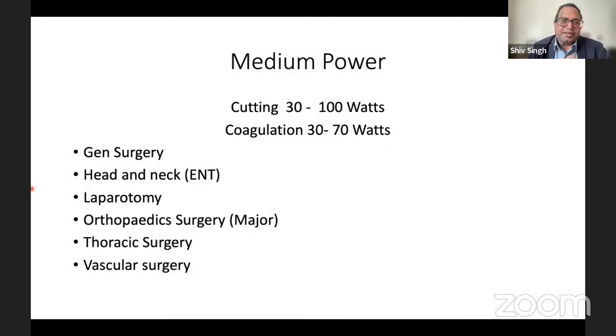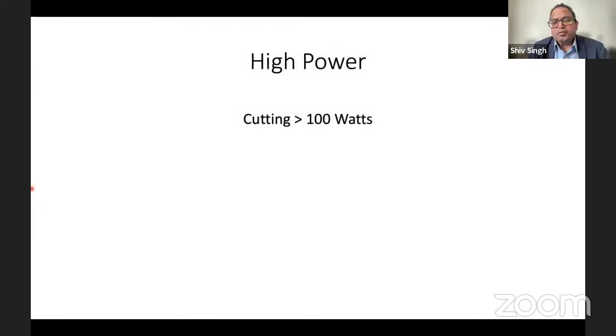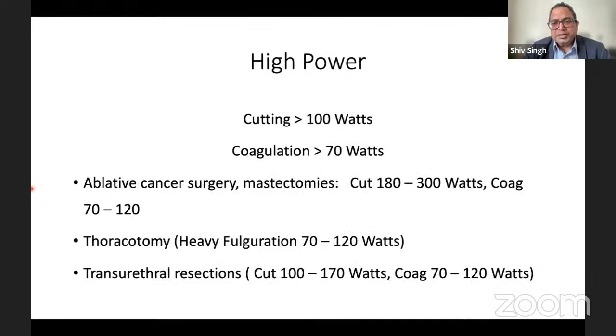It is used in ENT, laparotomies, orthopedic surgery, thoracic surgery, and vascular surgery. But sometimes you have to use very high power, and that's more than 100 watts for cutting and more than 70 watts for coagulation. This is sometimes used in ablative cancer surgeries and mastectomies, where they use 180 to 300 watts for cutting and 70 to 120 watts for coagulation. Thoracotomy, where you have to go between the ribs, uses heavy fulguration, again 70 to 120 watts. Transurethral resections use cutting at 100 to 170 watts and coagulation at 70 to 120 watts. So very high power is used.